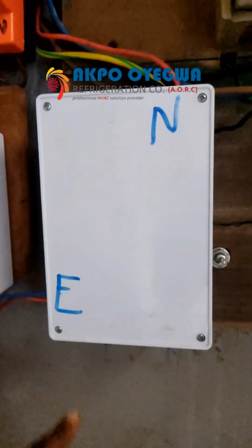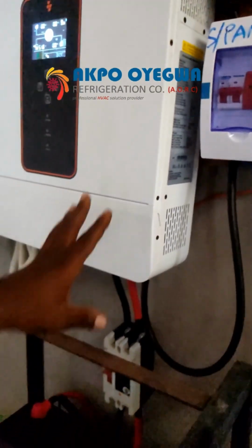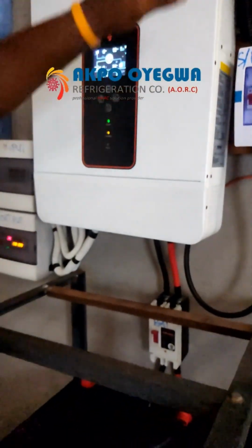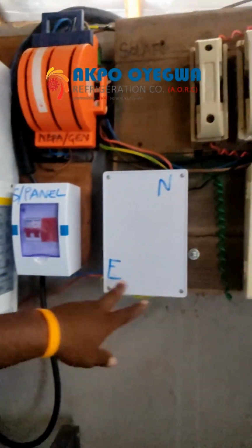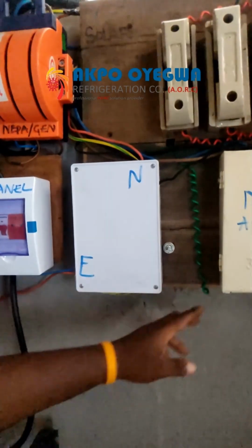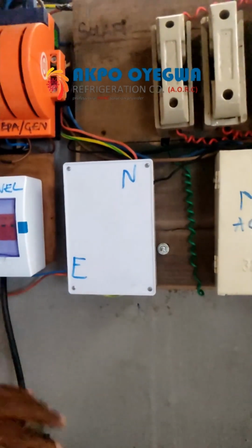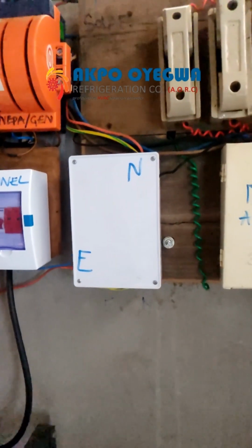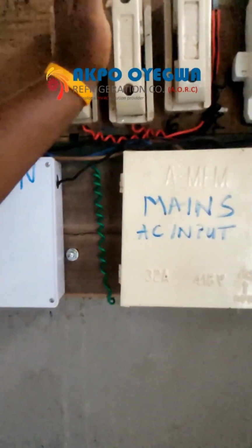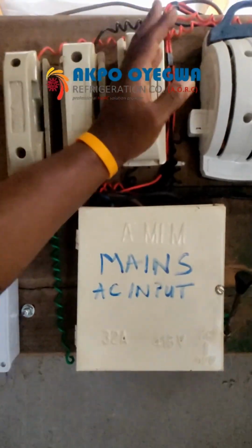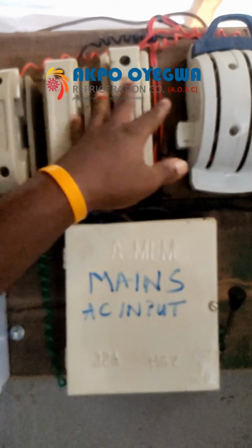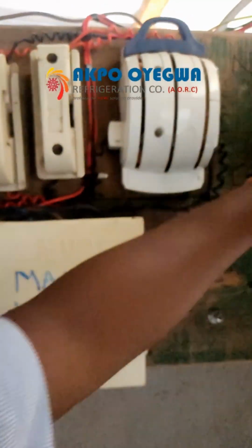We have the neutral and the earth. Every equipment you see here, the inverter, the cold room, everything is connected at this earthing point. The earthing point is taken out into the ground, so everything here is securely installed. Here, right here, we have 3 cutouts from the NEPA also. This is the 3-phase coming in. Here we can see NEPA and generator.